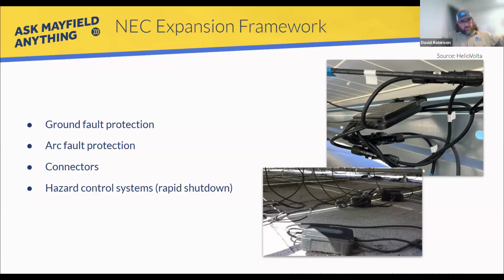And then you introduce rapid shutdown devices. The biggest problem is that before, your panels were connected in series and you could test at your positive and negative home runs in the combiner boxes and isolate that. But now you need extra equipment, which slows things down and introduces a lot more cost and time from an O&M standpoint, plus way more connectors and way more failure points.